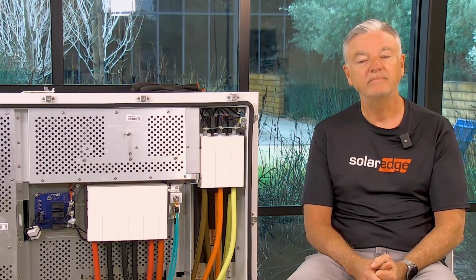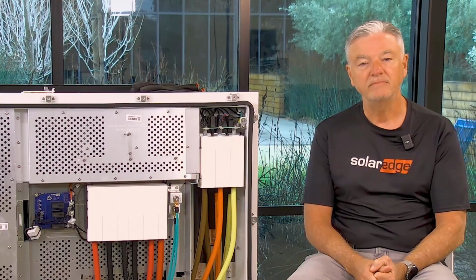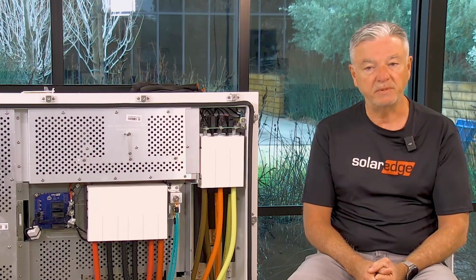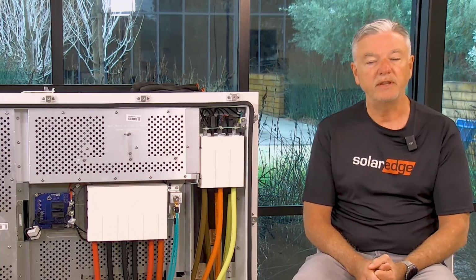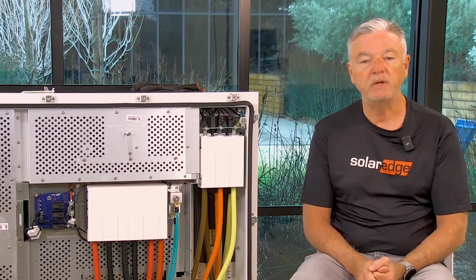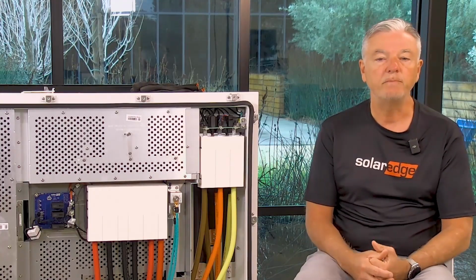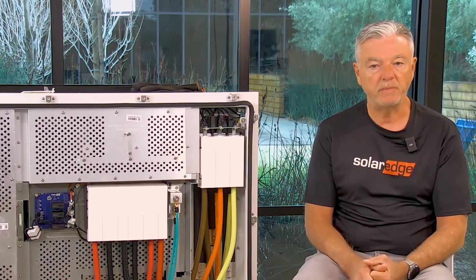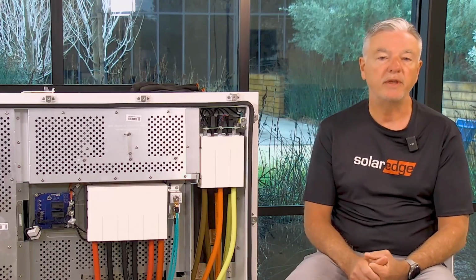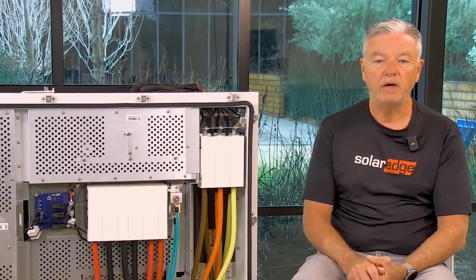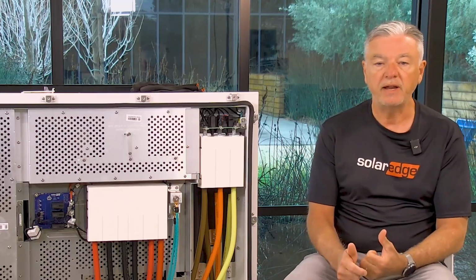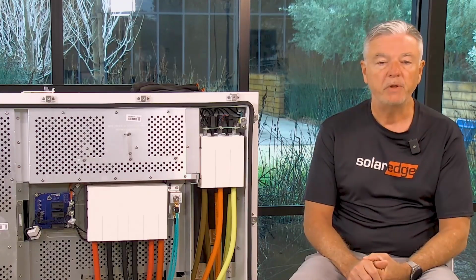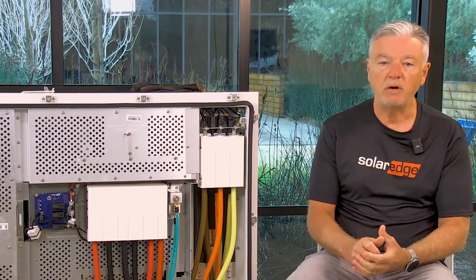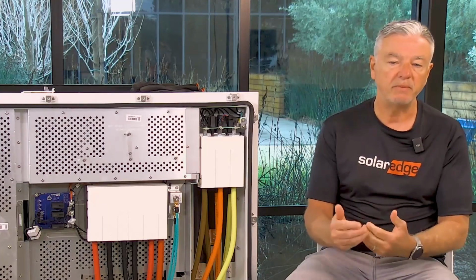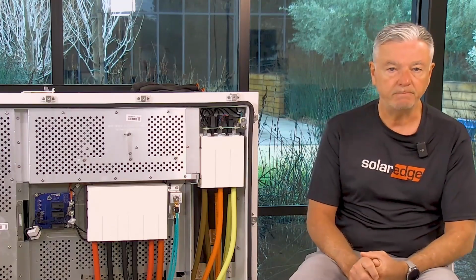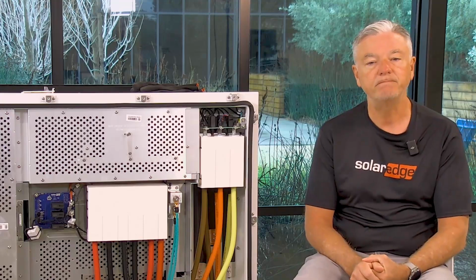Are there any special considerations if I'm using aluminum conductors? So yes, they should be sized properly, of course, and then as you're preparing the aluminum conductor, you strip it back like you normally would. Use a metal brush or maybe some emery cloth to clean off the conductor and remove any anodized material that's already on there. And then you would clean it with alcohol and then apply some type of an anti-corrosive coating on it and then apply your compression lug.